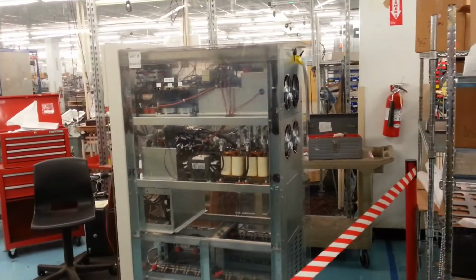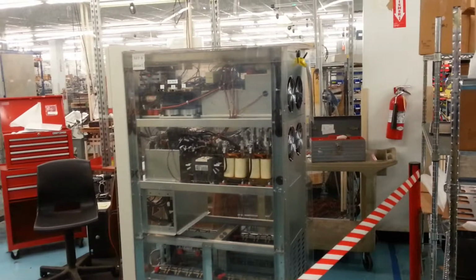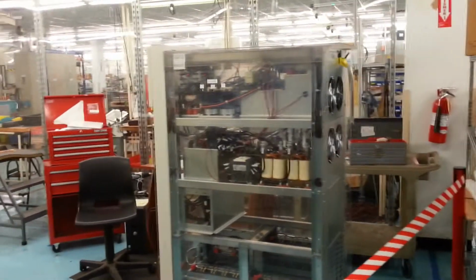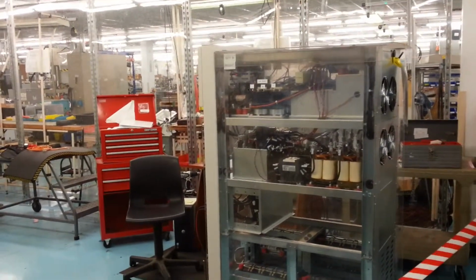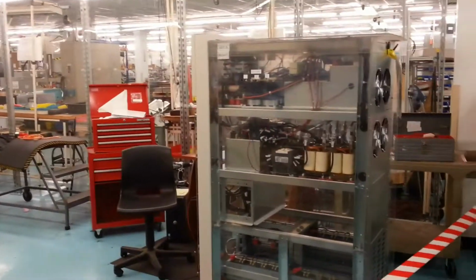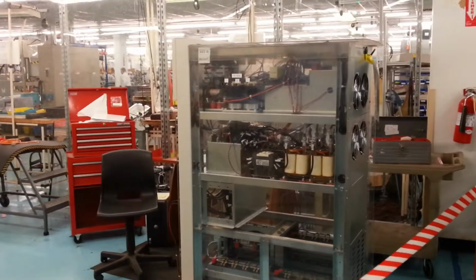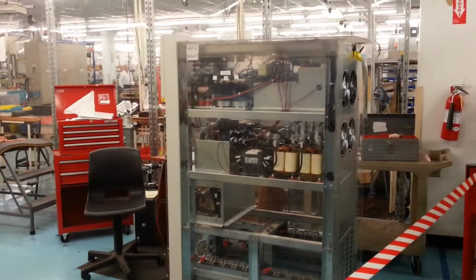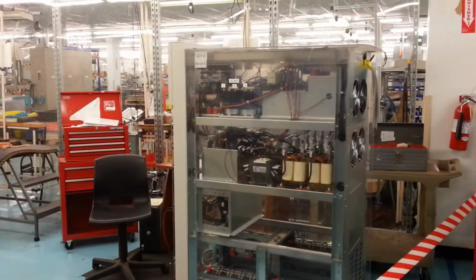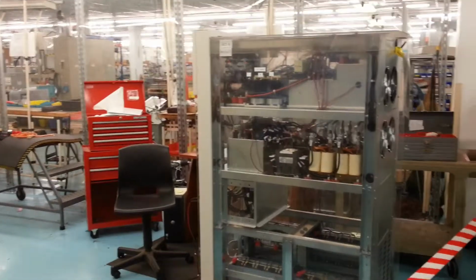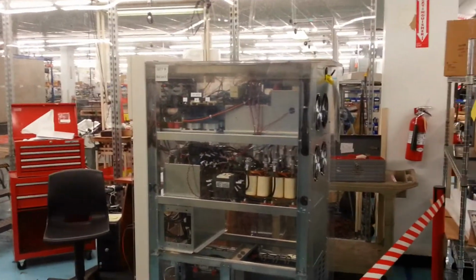So in lieu of a transformer, batteries. And in this case, this unit will probably have a battery backup somewhere around 6 to 8 minutes. And that's also proportional then to the customer's load. Less load, more runtime. And then they can parallel battery cabinets onto this if they choose. And it just has Lexan on it right now so they can actually get in there and touch it while it's running. They have little test holes all over the place. They stick the probes in.